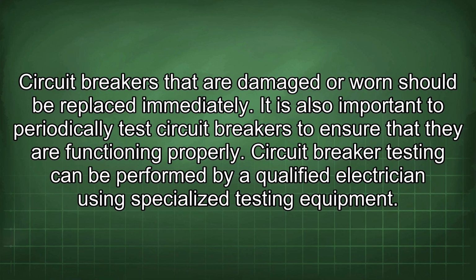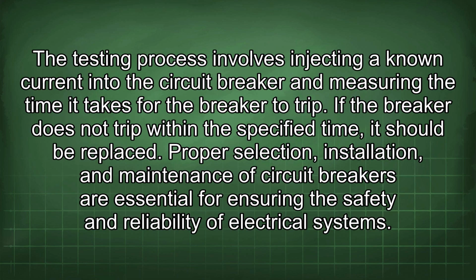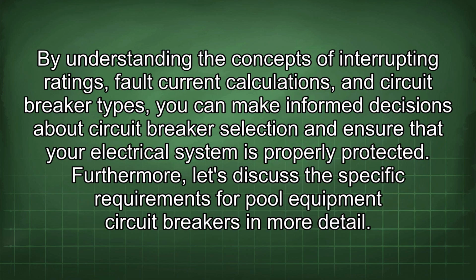Circuit breaker testing can be performed by a qualified electrician using specialized testing equipment. The testing process involves injecting a known current into the circuit breaker and measuring the time it takes for the breaker to trip. If the breaker does not trip within the specified time, it should be replaced. Proper selection, installation, and maintenance of circuit breakers are essential for ensuring the safety and reliability of electrical systems. By understanding the concepts of interrupting ratings, fault current calculations, and circuit breaker types, you can make informed decisions about circuit breaker selection and ensure that your electrical system is properly protected.